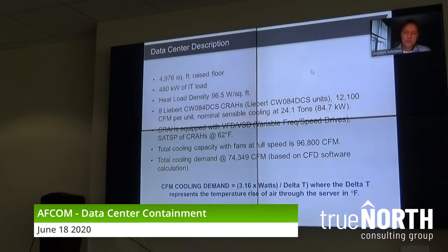you need. So instead of 158 CFM for 1 kW, if it's a brand new server, a blade server, very energy efficient, that delta T maybe is 40 degrees. So instead of 158, maybe you only need 79 CFM. So the CFD software can make calculations based on the heat load of that equipment. If you don't know that delta T, and here's the next thing, do all equipment manufacturers provide that delta T? Unfortunately, no. But it's not 20 degrees.